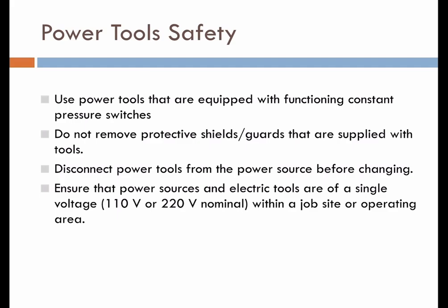Do not use portable electric power tools rated for use at a voltage exceeding 240 volts. Ensure that power sources and electric tools are of a single voltage — 110 volt or 220 volt nominal. Within a job site or operating area, match tools and extension cords to the supplied power source voltage.